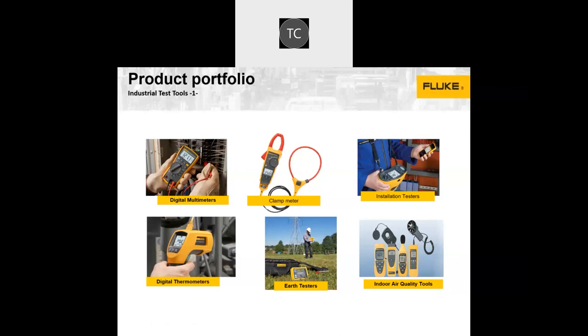In India, we have a customer who regularly buys this and uses more than 50 units, to my knowledge maybe more - a European elevator manufacturer who buys this product exclusively to test his tripping circuit. In elevators, everything is metallic, so if there's a short circuit, the person on the elevator can get killed. That's why during installation and factory testing, they use my product to verify whether their ELCB or tripping circuit is working. Many government customers also use it, but there's no standard as of now in India.